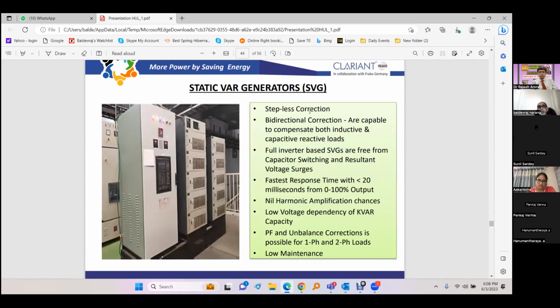This is called SVG or STATCOM. We are giving it to industry today, and we have given it to renewable plants also for fine correction. Here the power factor has become very important because of the kVAh billing. We can maintain power factor close to unity with this. Rough correction we do with either contactor-based automatic systems or thyristor-based systems, and very fine correction we do with this.